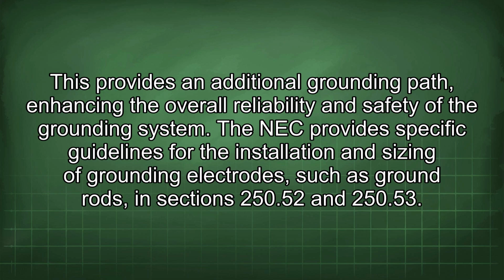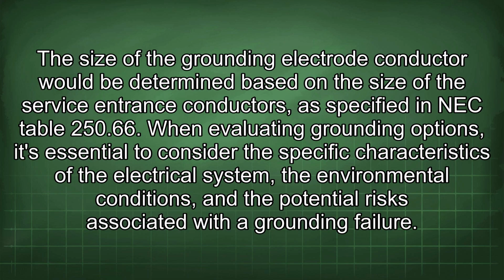The NEC provides specific guidelines for the installation and sizing of grounding electrodes such as ground rods in sections 250.52 and 250.53. The size of the grounding electrode conductor would be determined based on the size of the service entrance conductors, as specified in NEC Table 250.66. When evaluating grounding options, it's essential to consider the specific characteristics of the electrical system, the environmental conditions, and the potential risks associated with the grounding failure.